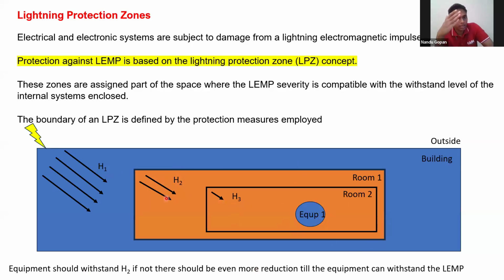So this is what the LPZ zone concept works in. You will categorize this building as zone 1, this room as zone 2, and this room 2 as zone 3. So you categorize it based on how sensitive the equipment is. If the equipment is not sensitive, just a normal motor, you can keep it in zone 1 - you don't need zone 2 and zone 3, you don't need 3 rooms.